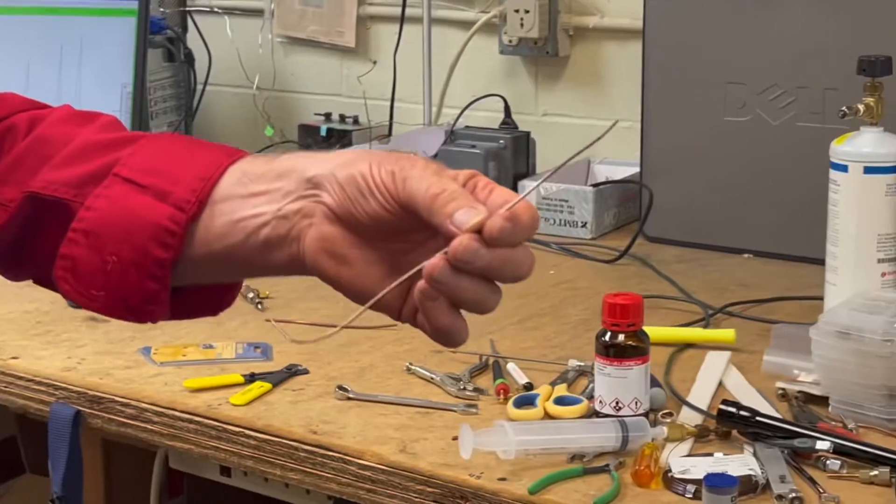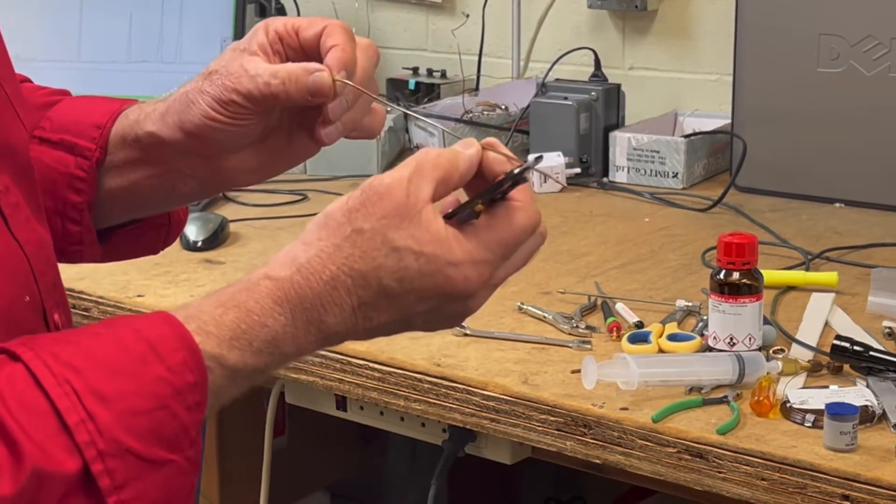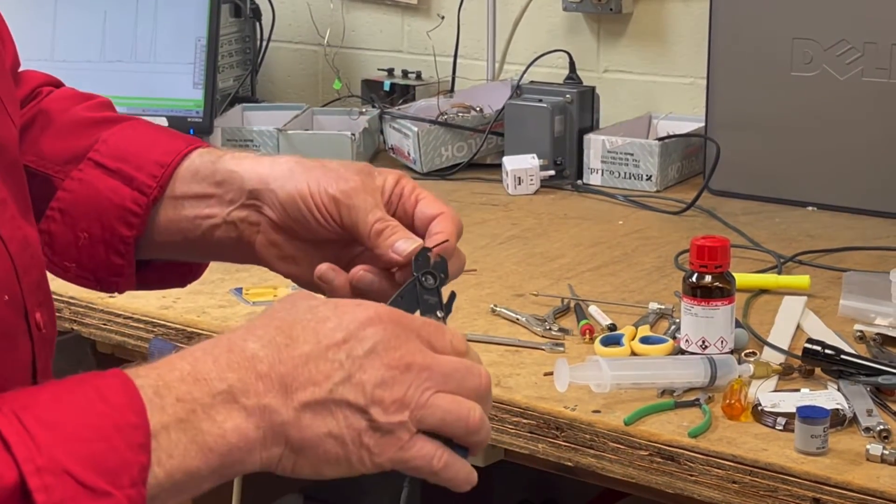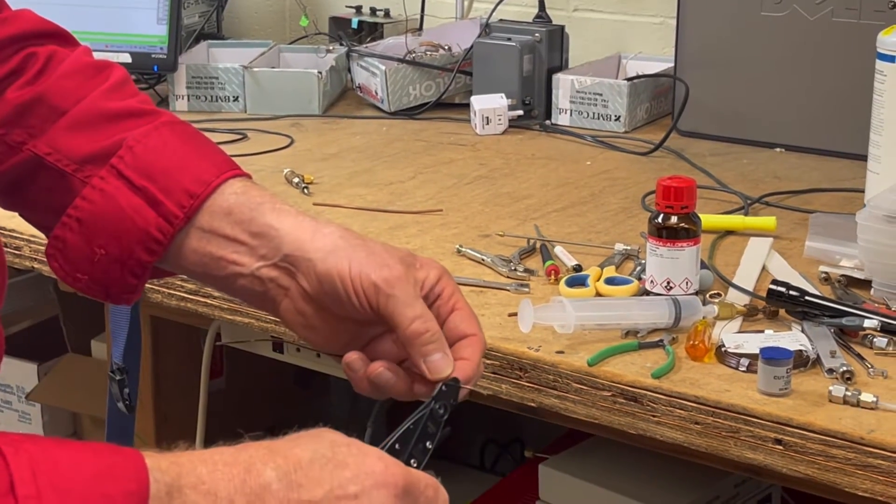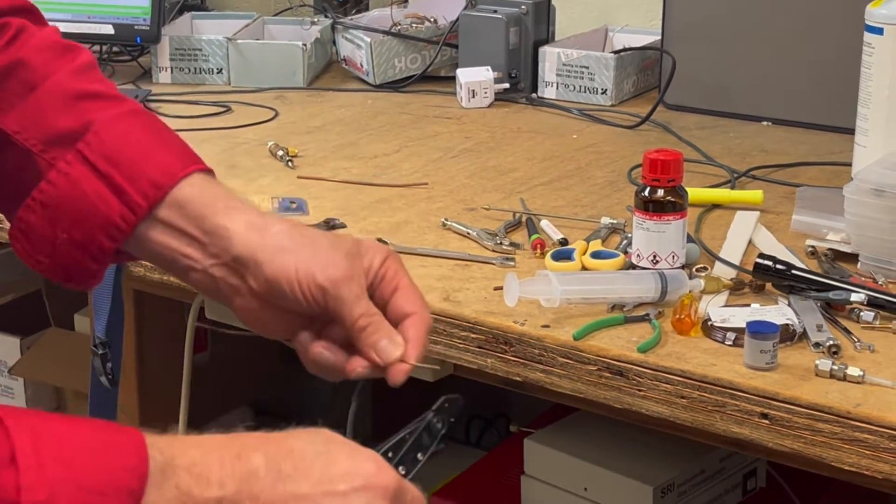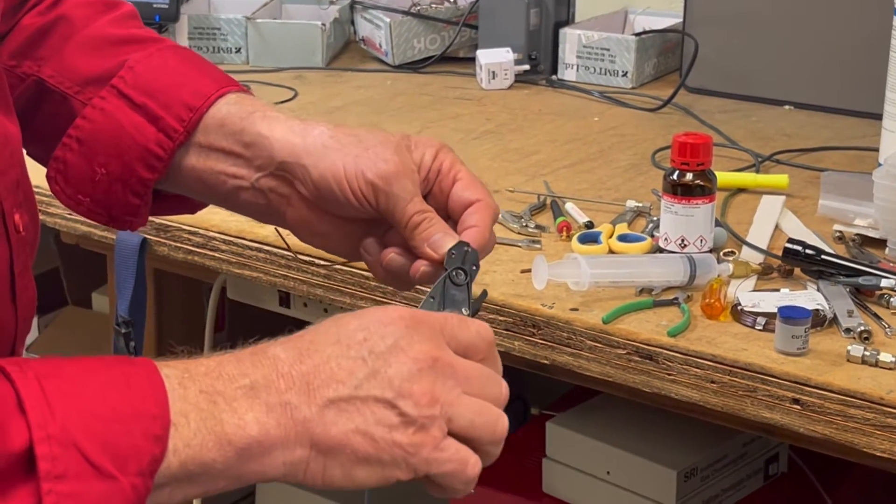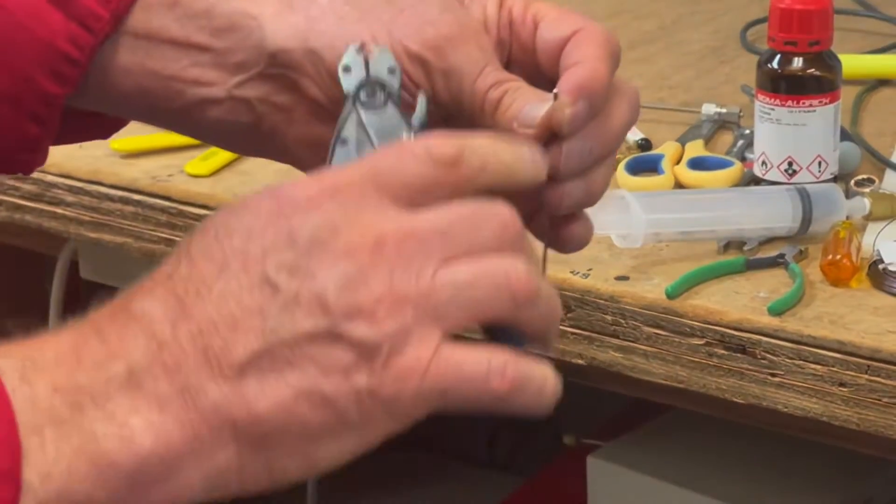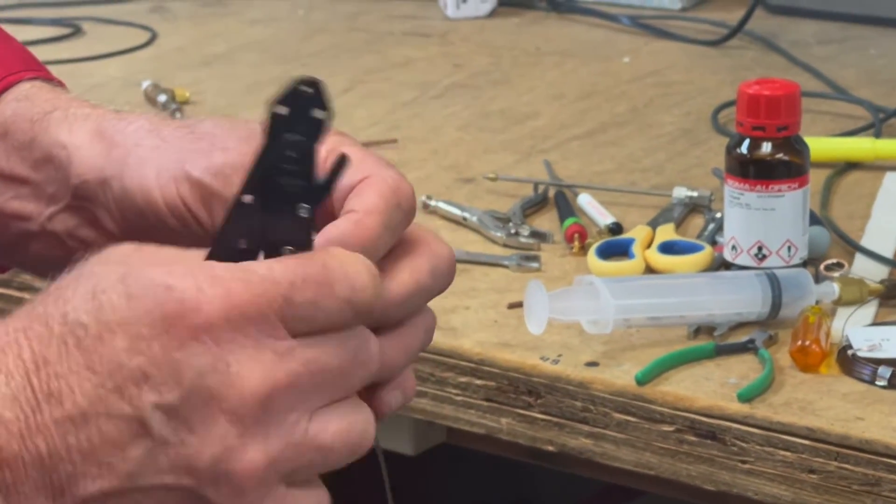Inside the GC there's a variety of places where there's 16th inch stainless steel tubing, so this is also easy to cut with this cutter. You position the tubing cutter 90 degrees to the tube and then you cut fast and hard. If you want to really make a nice cut you go about a millimeter or two from the end, same thing, cut really fast and you get a really nice cut where it doesn't smear the hole out or close the hole.